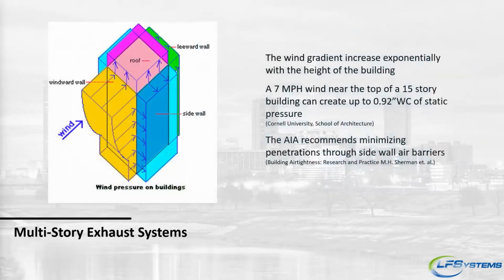But the one thing you can't get by is a study. AIA basically says that you should minimize the penetrations in the sidewall of your building because that just creates more areas of leakage into your space. Also, Cornell University did a study and found that a 7-mile-an-hour wind can create almost 9/10 of an inch back pressure on the exhaust. Well, if you remember back a few slides, the maximum amount of back pressure that a residential dryer can handle is about 9/10 of an inch. So even if you have that dryer up against the exterior wall and you go straight out the sidewall, you're still going to have potential issues because of that windward wall.